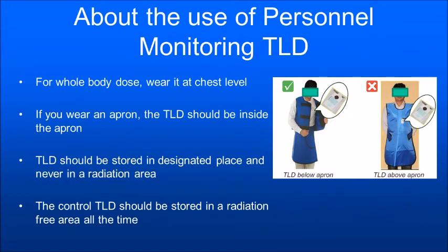Let us now look at how this personal monitoring device is to be used by each individual. If you are measuring whole body dose, it has to be worn at the chest level. And if you are wearing an apron, the TLD should be inside the apron and not outside the apron as it is here. TLD should be stored in a designated place and never in any radiation area.